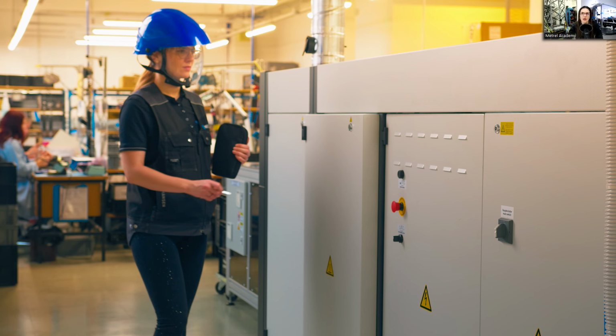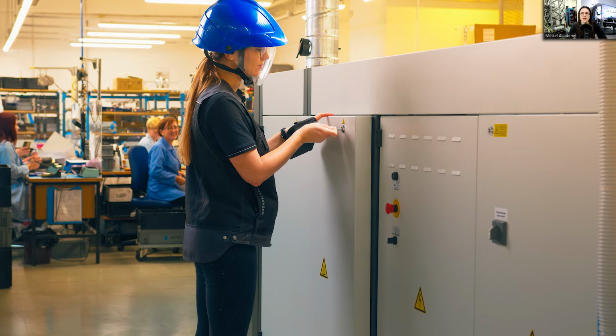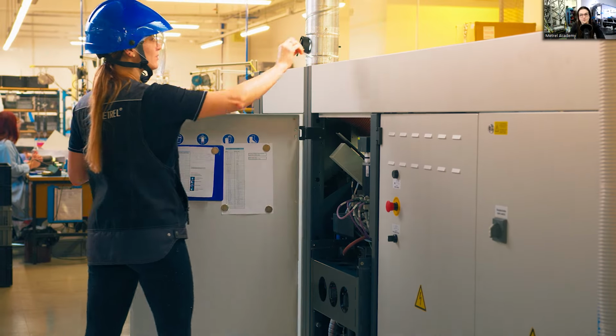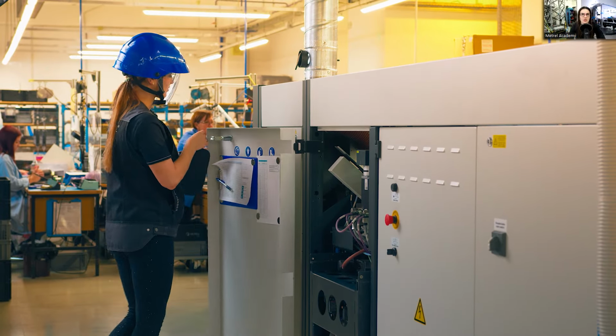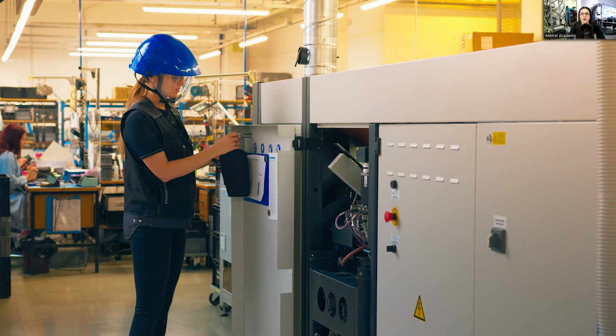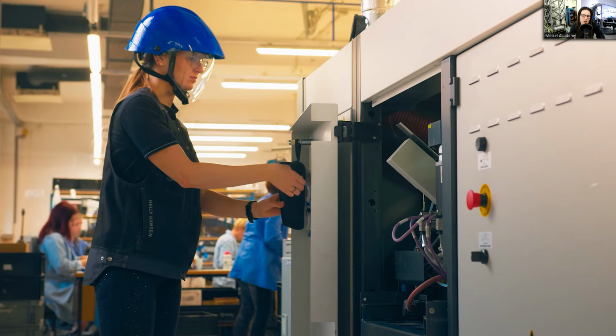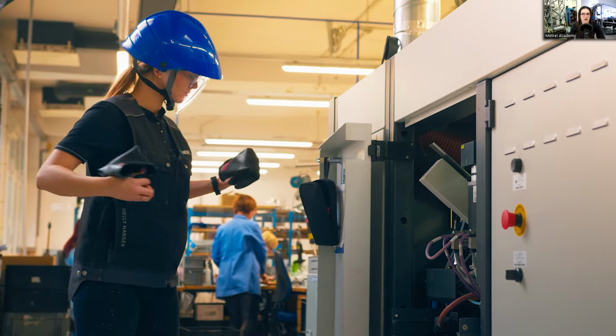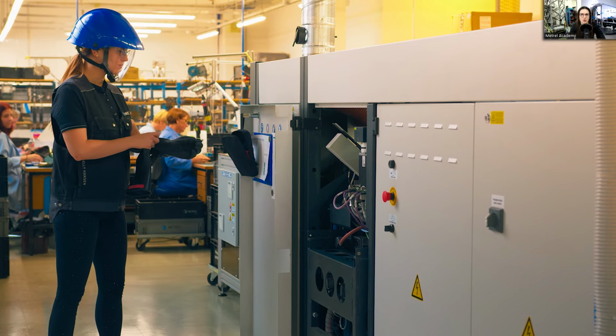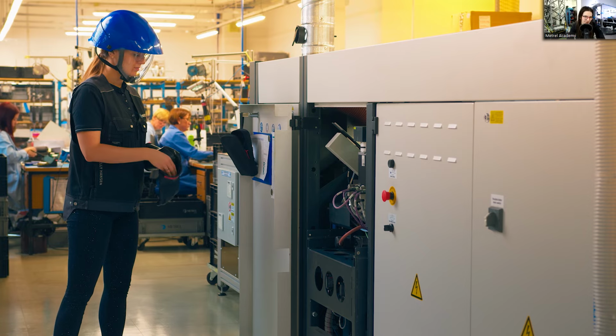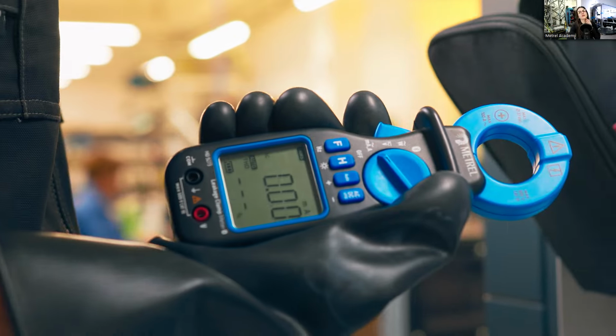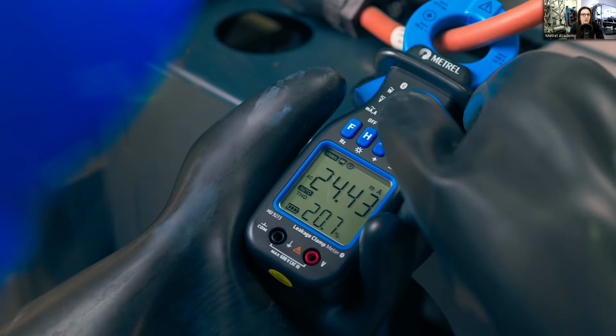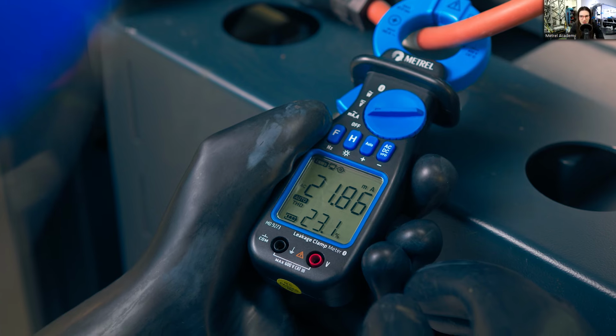The machine I'm going to show you is actually one of the machines we have in the Metrel production hall. Working within it is relatively dangerous. We are close to the heater and we are close to the electrical installation, so I need to use protective measures for both of these dangers. The supply wire, in this case, is very easy to recognize, and this makes the differential method ideal for this case.